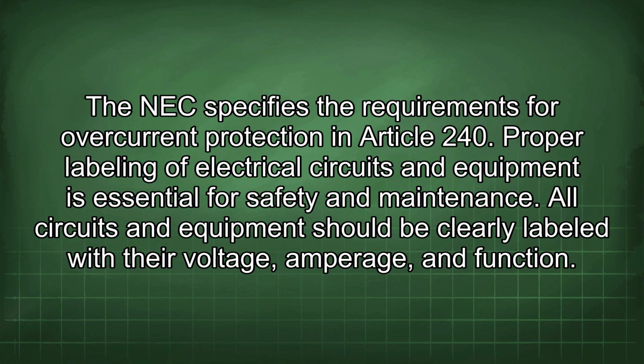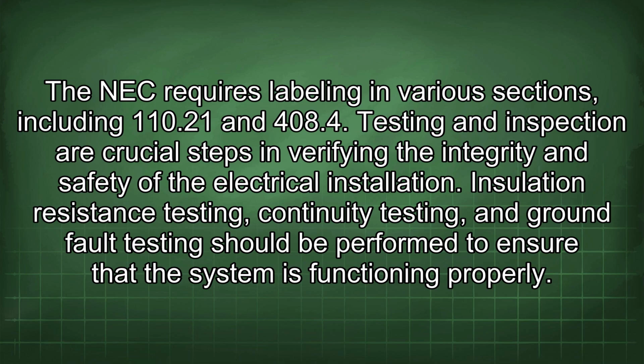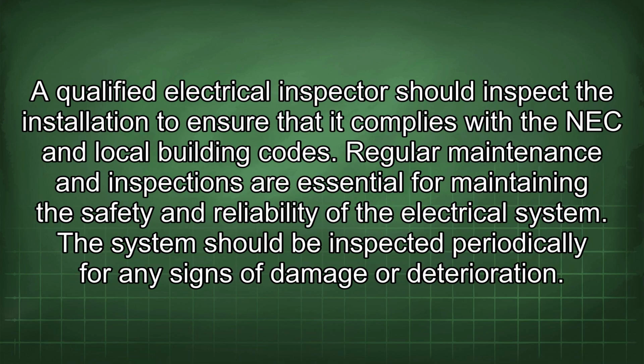Proper labeling of electrical circuits and equipment is essential for safety and maintenance. All circuits and equipment should be clearly labeled with their voltage, amperage, and function. The NEC requires labeling in various sections, including 110.21 and 408.4. Testing and inspection are crucial steps in verifying the integrity and safety of the electrical installation. Insulation resistance testing, continuity testing, and ground fault testing should be performed to ensure that the system is functioning properly. A qualified electrical inspector should inspect the installation to ensure that it complies with the NEC and local building codes.